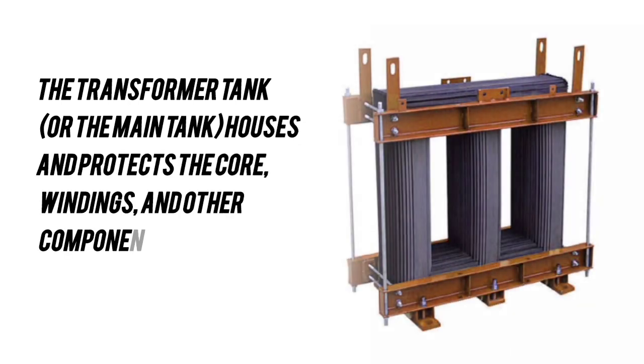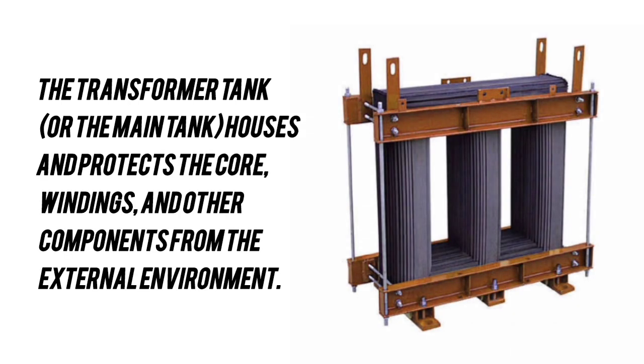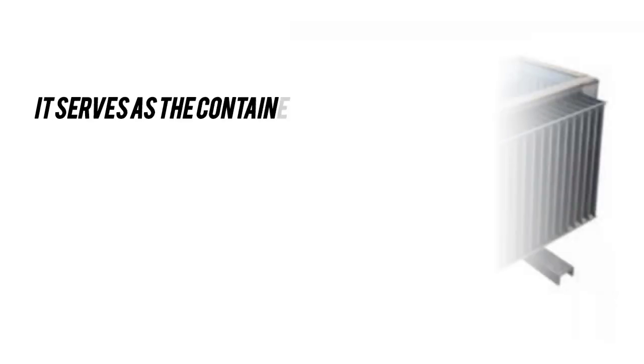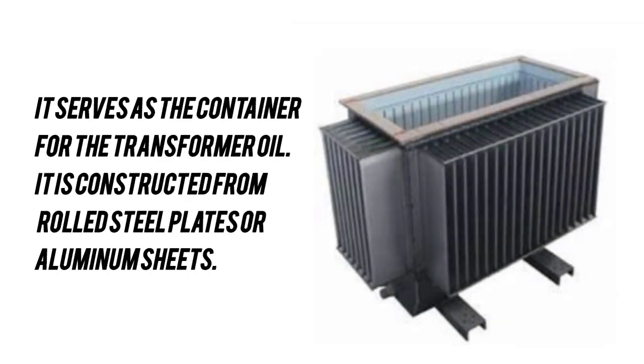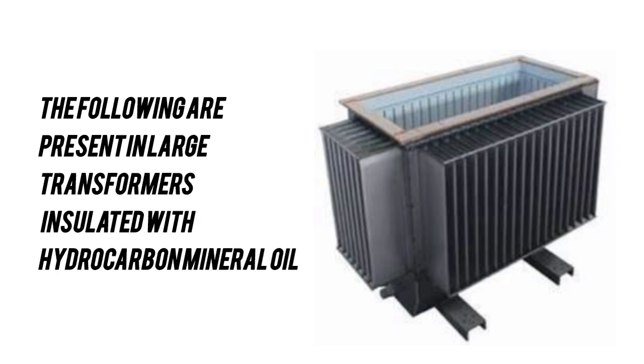Transformer tank. The transformer tank, or the main tank, houses and protects the core, windings, and other components from the external environment. It serves as the container for the transformer oil. It is constructed from rolled steel plates or aluminum sheets. The following are present in large transformers insulated with hydrocarbon mineral oil.